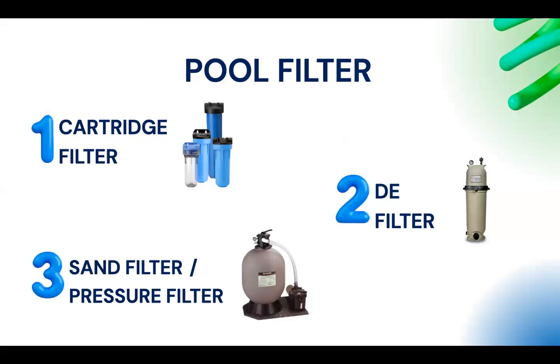If you don't design a sand filter properly it cannot catch small particles. Sand can also become a biofilter — it harbors bacteria growth, and the sand will start to clump or coagulate together, so water just passes through without being filtered. If your pool looks the same after 12 hours of sand filtering, there is a problem — the filter is not filtering. You need to either backwash or do a proper cleaning and start filtering again.